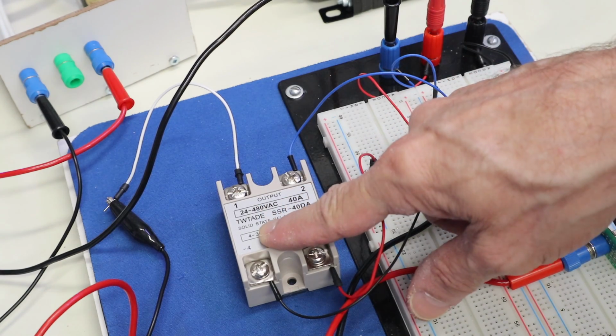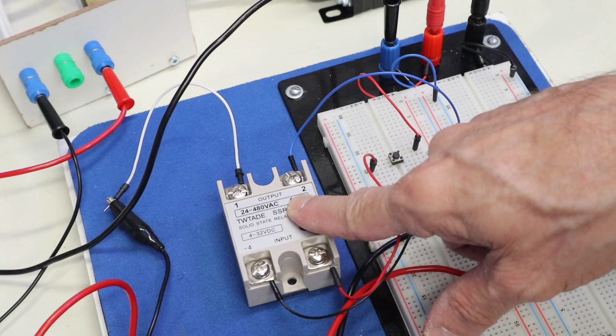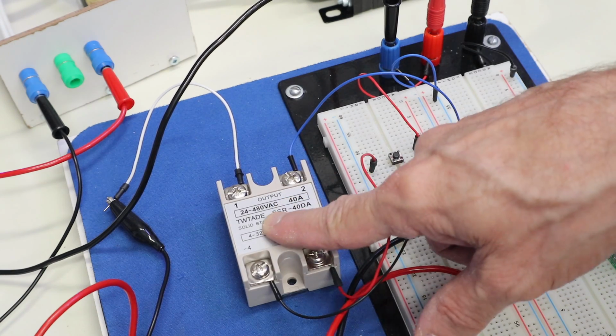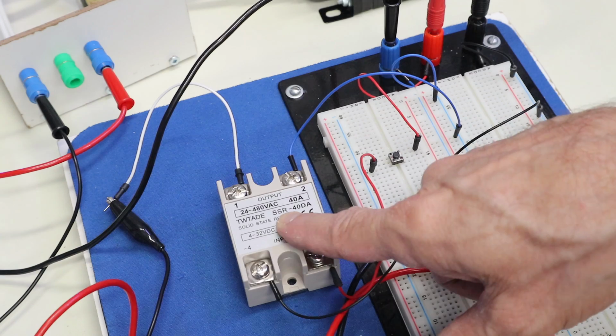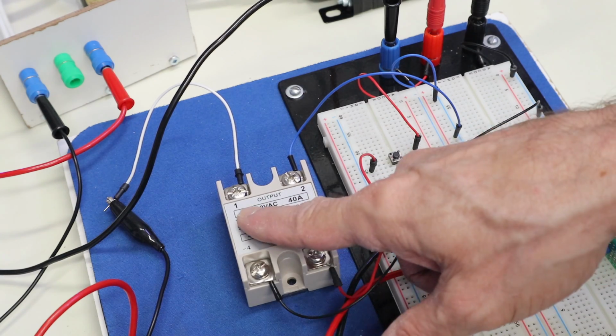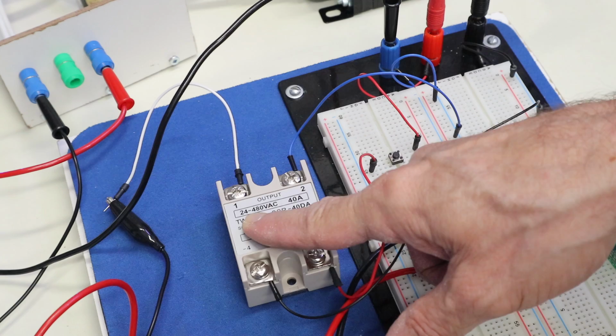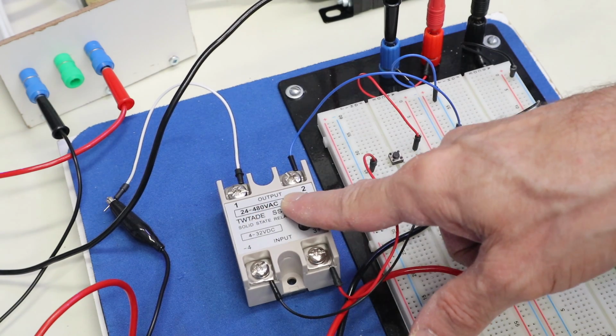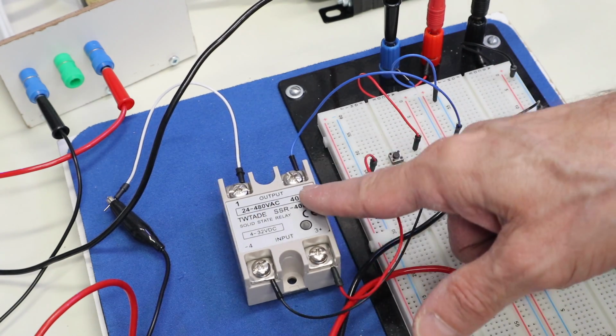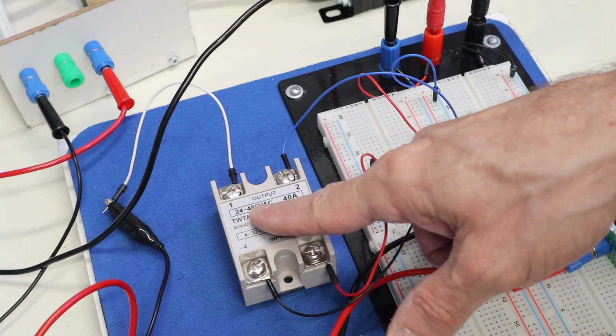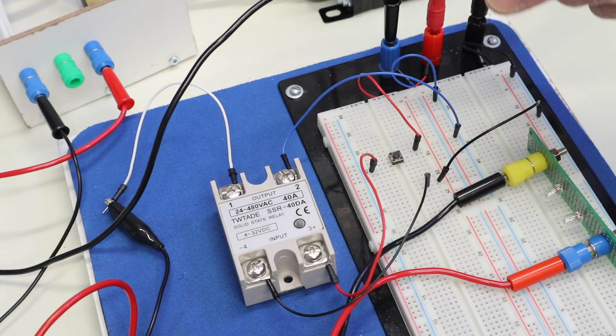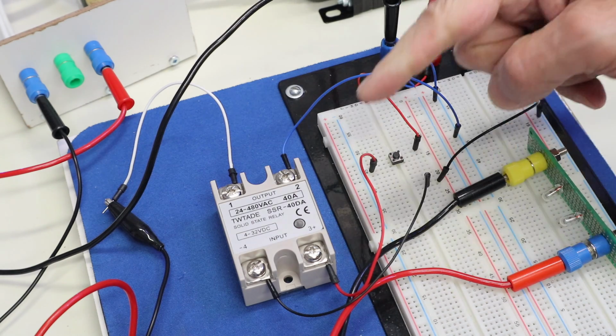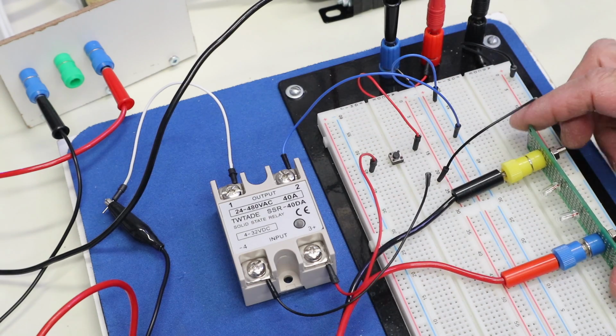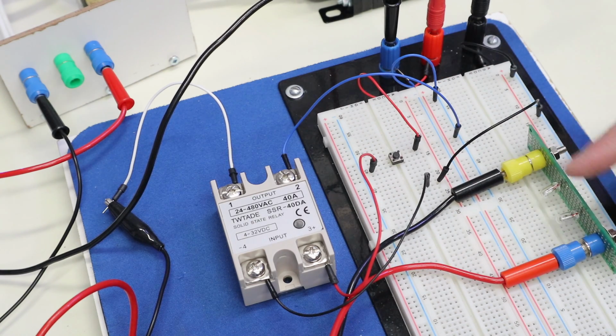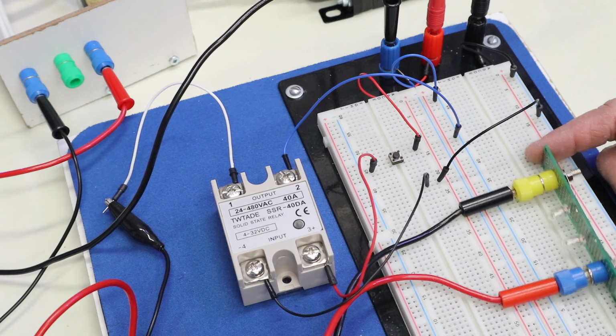Note that this starts off at 4 volts, so this particular solid-state switch wouldn't be particularly good for use with 3.3 volt logic. The output here is rated from 24 to 480 volts AC at up to 40 amperes. I'm certainly not drawing 40 amperes, but I've met the minimum voltage requirement. This is my 28 volt transformer, which as we saw earlier is really more like 35 volts, and my load is again my two 28 volt incandescent light bulbs.